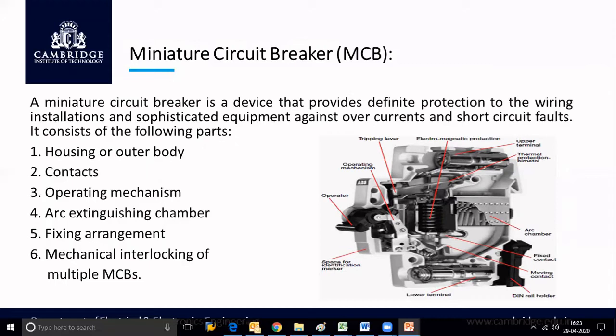That is why the next advancement over the fuse is the use of the miniature circuit breaker. The miniature circuit breaker, or shortly MCB, is a device that provides definite protection to wiring installations and sophisticated equipment against overcurrents and short circuit faults. The main purpose of this MCB is to break the circuit under abnormal conditions such as overcurrent, that means overload conditions, or short circuit conditions, or any other types of faults occurring in the circuit.